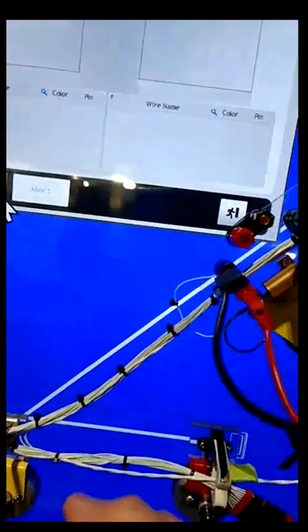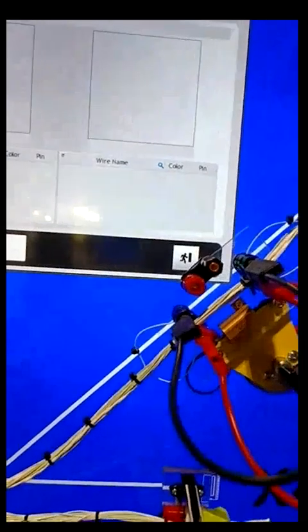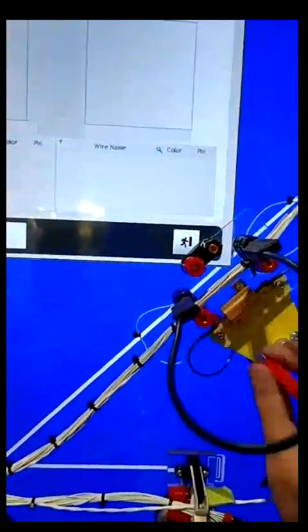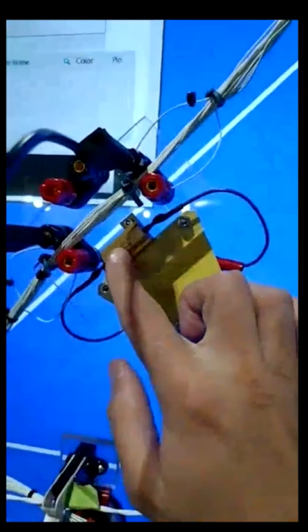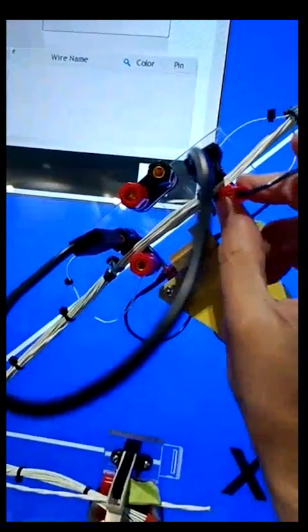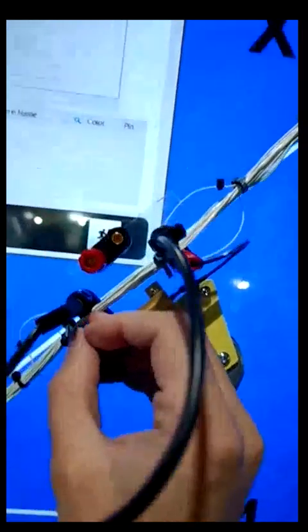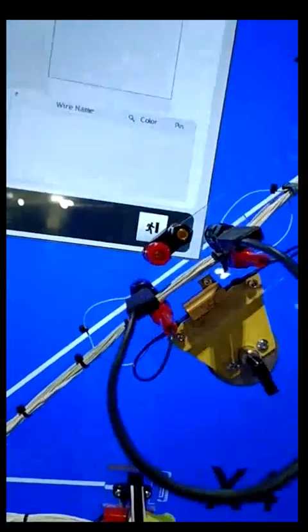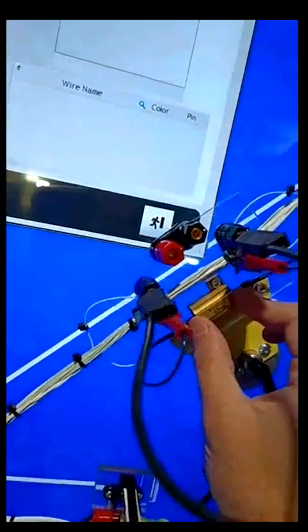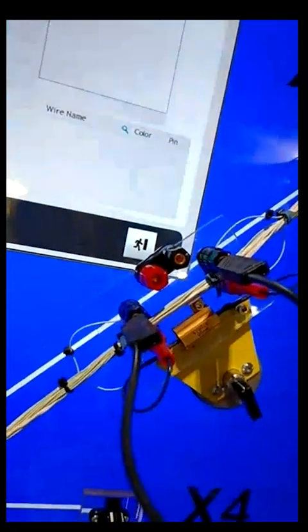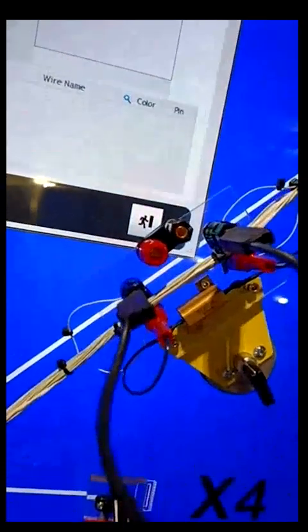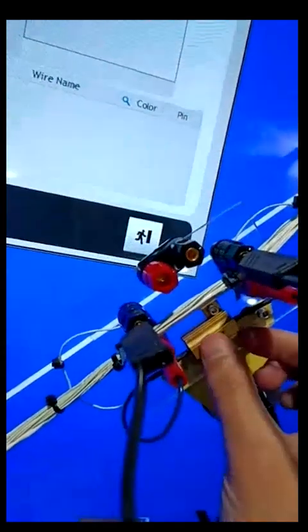The last test we have on the board is like when you crimp a contact: if you do it incorrectly, too fast, or with the wrong tool, the resistance of the wire will be too high. So that's why I have a resistor here on a cable. Instead of having a wire connecting red to red, I'll plug in the resistor, meaning there is continuity, there's a wire, but the resistance is too high because the contact isn't crimped or inserted correctly. So that's a continuity test, but for resistance.